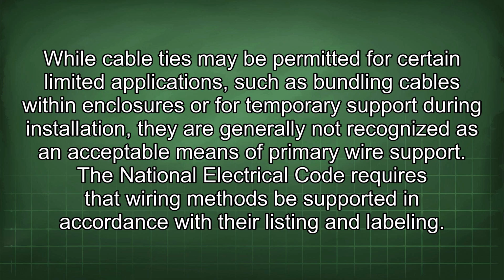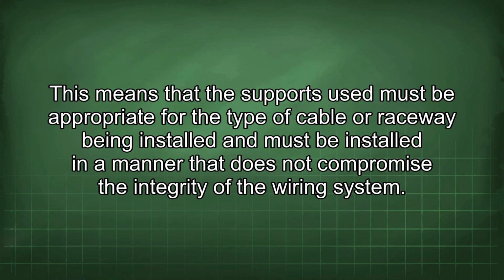The National Electrical Code requires that wiring methods be supported in accordance with their listing and labeling. This means that the supports used must be appropriate for the type of cable or raceway being installed and must be installed in a manner that does not compromise the integrity of the wiring system.